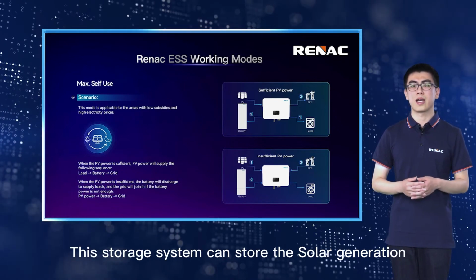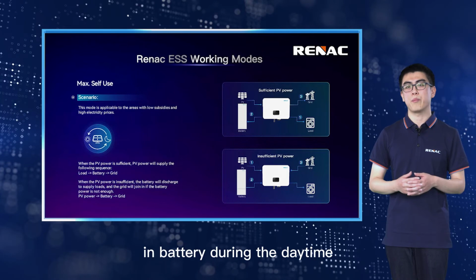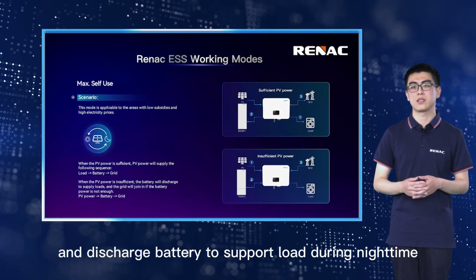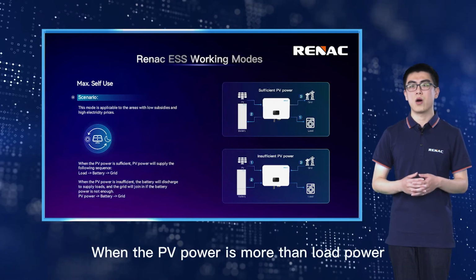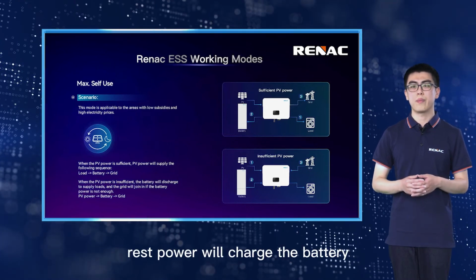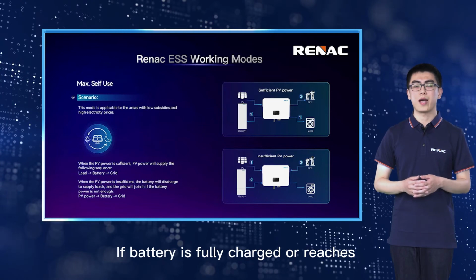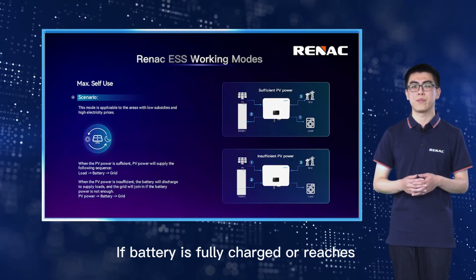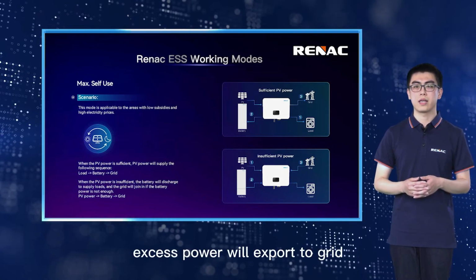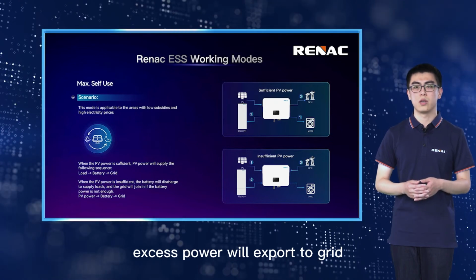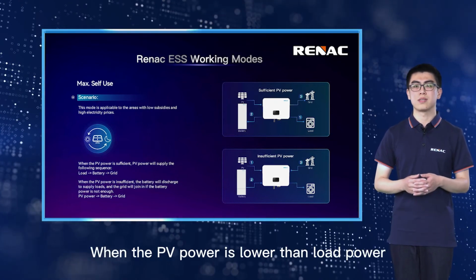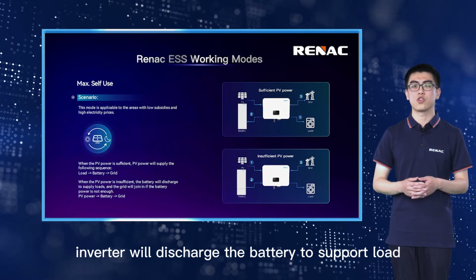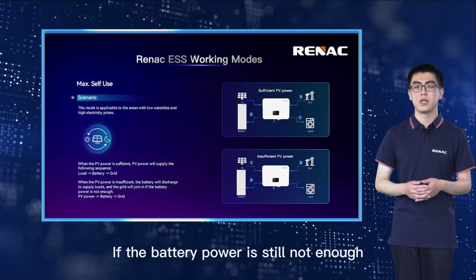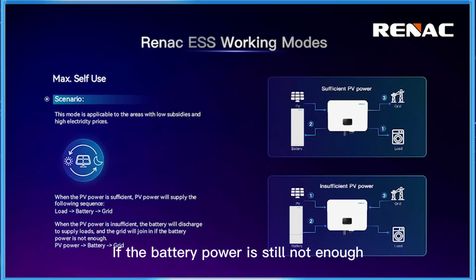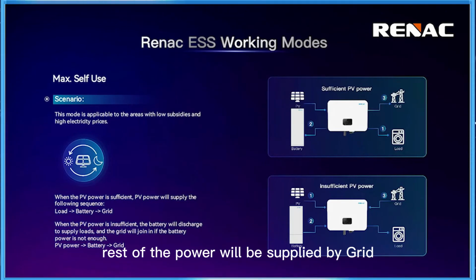This storage system can store the solar generation in battery during the daytime and discharge battery to support load during nighttime. When the PV power is more than load power, rest power will charge the battery. If battery is fully charged or reaches maximum charge power, excess power will export to grid. Once the PV power is lower than load power, inverter will discharge the battery to support load. If the battery power is still not enough, rest of the power will be supplied by grid.